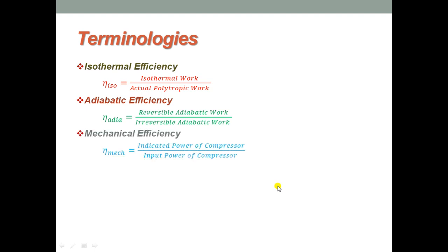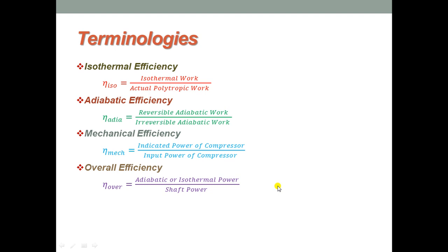The third efficiency is mechanical efficiency, defined as the ratio of indicated power of the compressor to the power input to the compressor. Next is overall efficiency, defined as the ratio of adiabatic or isothermal power to shaft power. This gives the overall efficiency of a compressor.